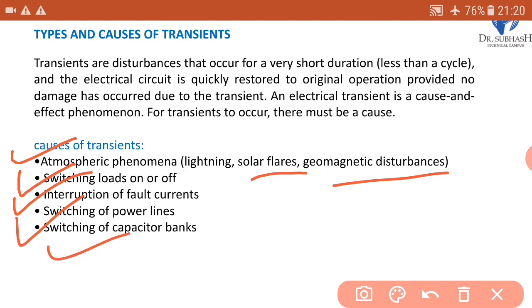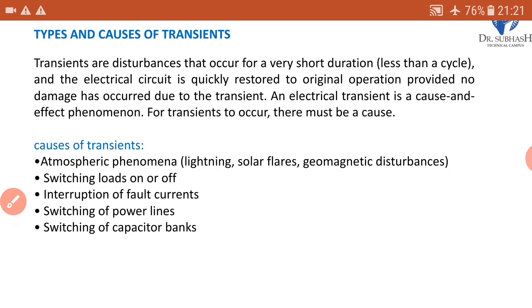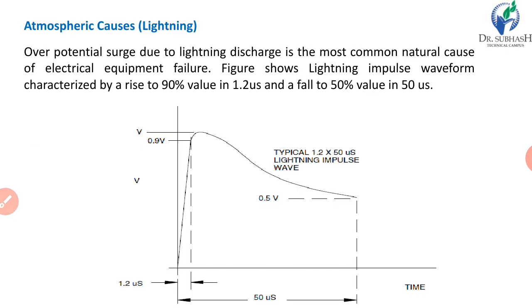And the last one is switching of capacitor banks. For power factor correction, we use capacitor banks in a power system. Due to this switching, a transient may be generated. In all these cases, most of the transients are generated due to switching of different types: switching of loads, switching of power lines, or switching of capacitor banks. So keep this in mind. Now we will see these causes in some detail. First one is atmospheric causes or lightning.